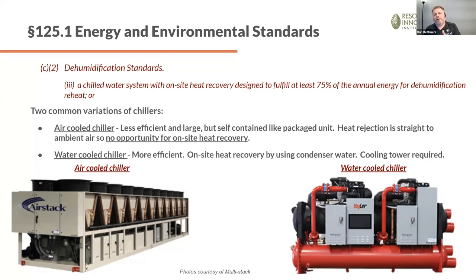What's much easier is using a water-cooled chiller, because there, as you can see, there's the red bundle, the red barrel, and the black barrel. The red barrel is my condenser, so that's where the heat's getting rejected to. It creates this hot water that normally I'd send to a cooling tower to reject the heat outside, but I could take that hot water and run it back around and use it to heat my spaces. So in that case, it is a great opportunity for on-site heat recovery.